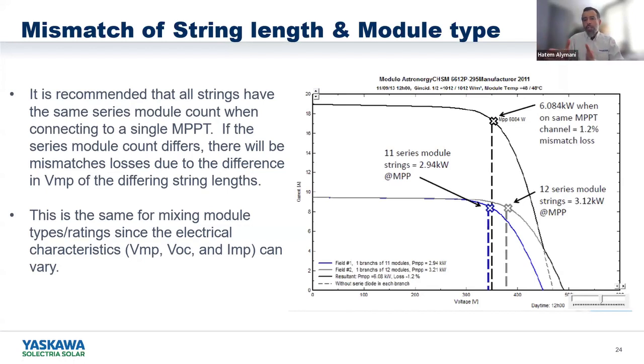But if we put the two strings in one MPPT, then we're going to have some voltage mismatch, and our maximum power point tracking is going to be skewed, and that will reduce the overall production. So this could cause up to 1.2% of losses that we can easily avoid. Of course, this is just a small example of 11, 12 modules. If we go all the way to 16, 17 modules, the losses will increase as well. So the most important thing is that in the same MPPT, we really have to make sure that the string lengths are the same and we are using the same exact modules.